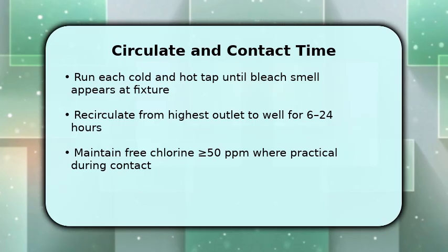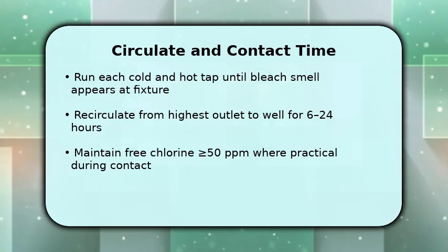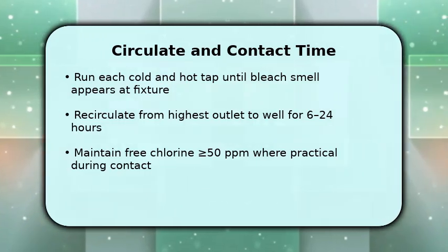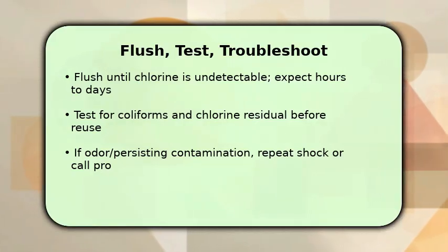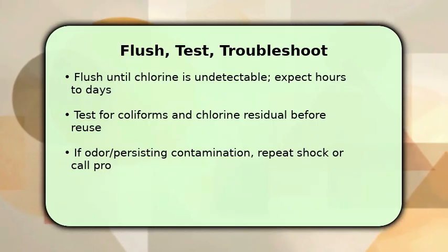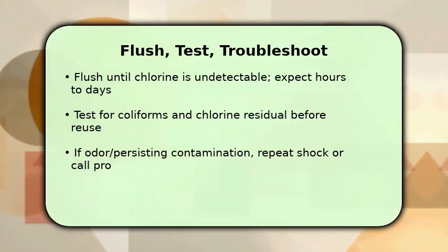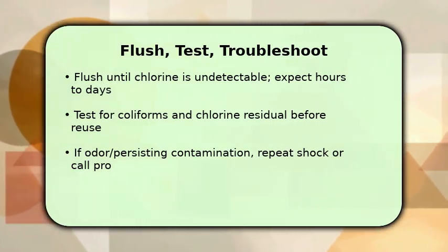Open faucets and run water until there is no bleach odor and chlorine readings fall to background levels. This can take hours or longer. Then collect samples for bacteriological testing and confirm chlorine residual is negligible before normal use.